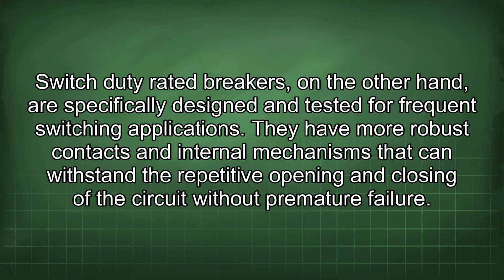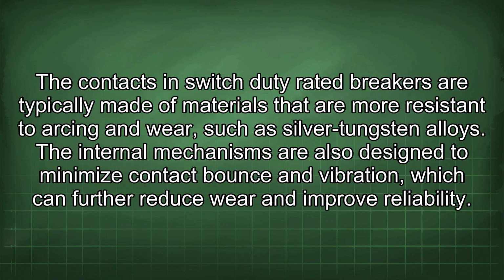Switch-duty rated breakers, on the other hand, are specifically designed and tested for frequent switching applications. They have more robust contacts and internal mechanisms that can withstand the repetitive opening and closing of the circuit without premature failure. The contacts in switch-duty rated breakers are typically made of materials that are more resistant to arcing and wear, such as silver tungsten alloys. The internal mechanisms are also designed to minimize contact bounce and vibration, which can further reduce wear and improve reliability.